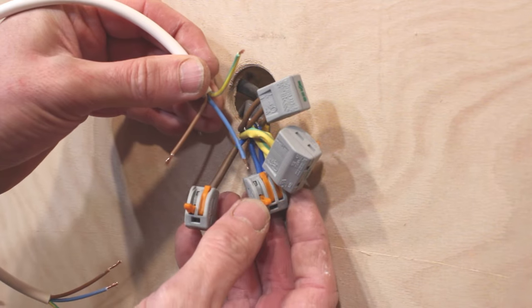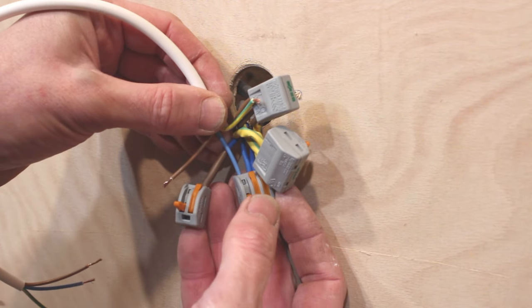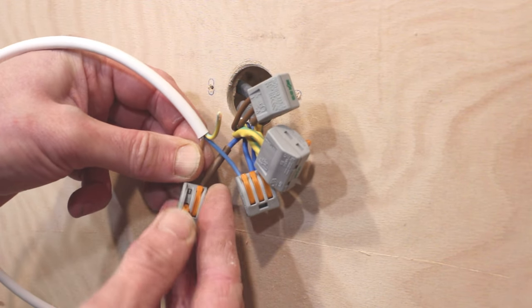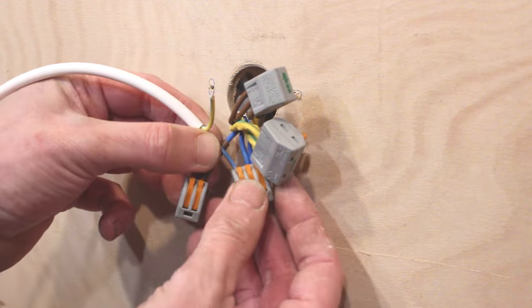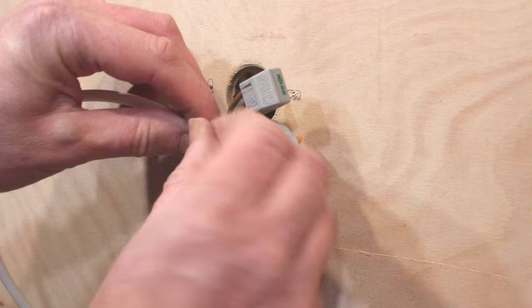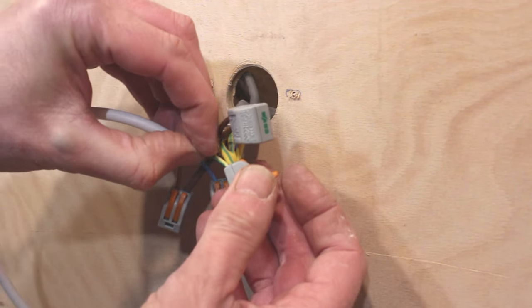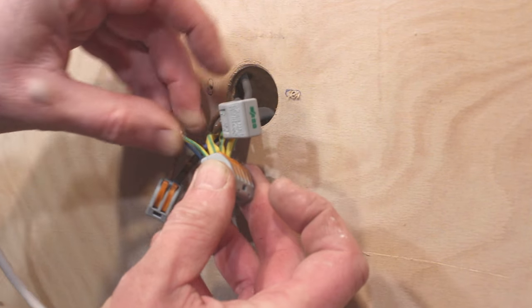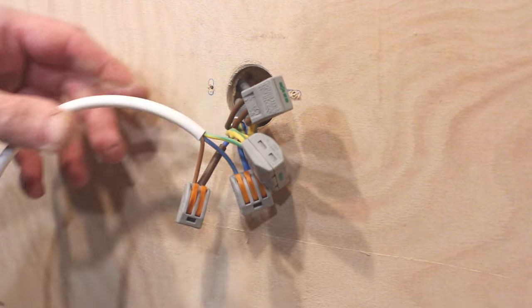So let's take the piece of flex. Attach the neutral to the neutral block. And this switch live part of it to the switch live block making sure everything is secure. In this case we have got an earth so we'll connect up the earth to the main earth block. Like so.